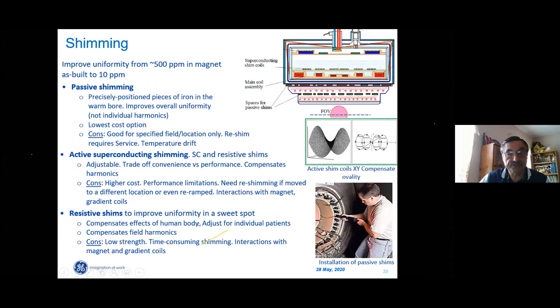And shimming. When we build this complicated magnet, we can achieve uniformity in the magnet as built of about 500 parts per million. And we need to design it to improve shimming to 10 parts per million. A couple of methods are used, so-called passive shimming. Precisely positioned shim coils are located here, superconducting shims are located here, and passive shims are located here. This is the place for these small pieces of iron, and that's exactly what we do.